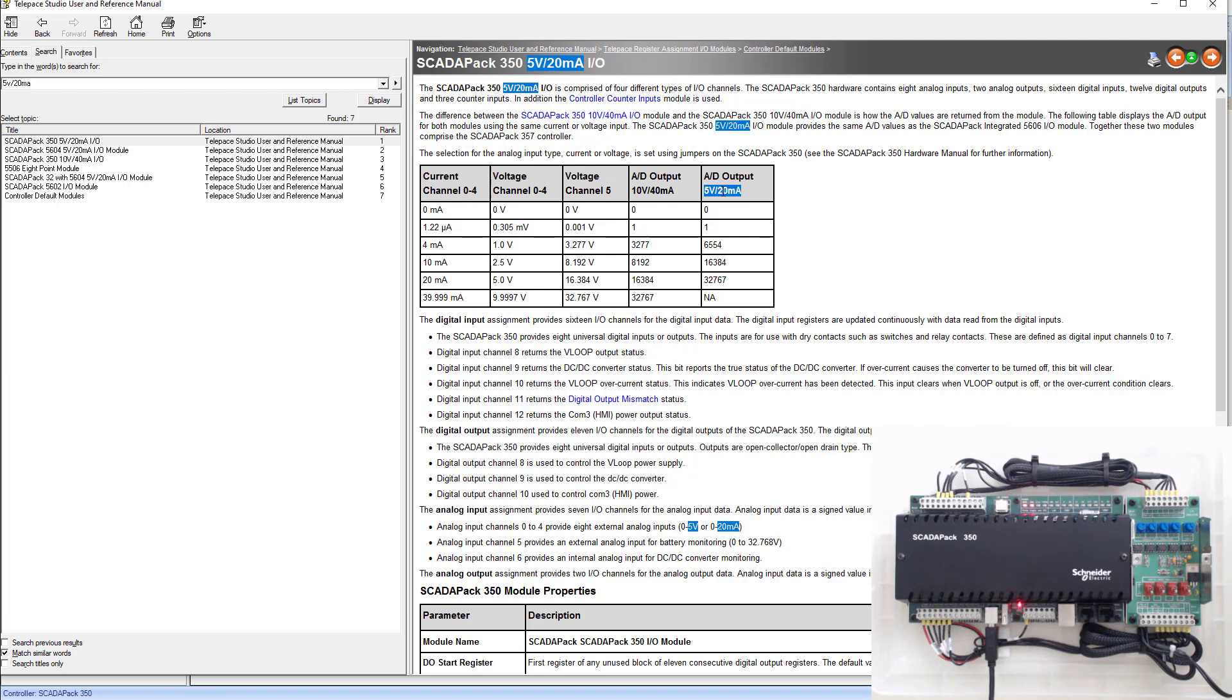We know that we're using the 5 volt 20 milliamp, not the 10 volt 40 milliamps. We know that 4 milliamps is 6554 and 20 milliamps is 32767. So go ahead and write that down. We'll be referencing that later in these labs as well.